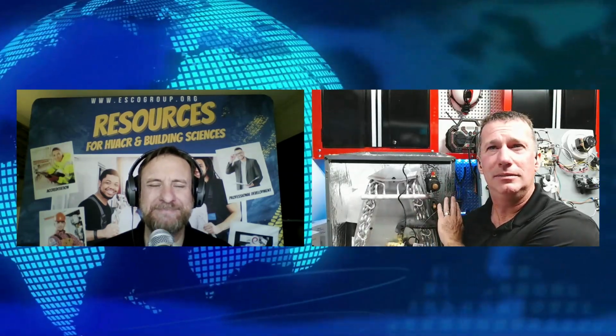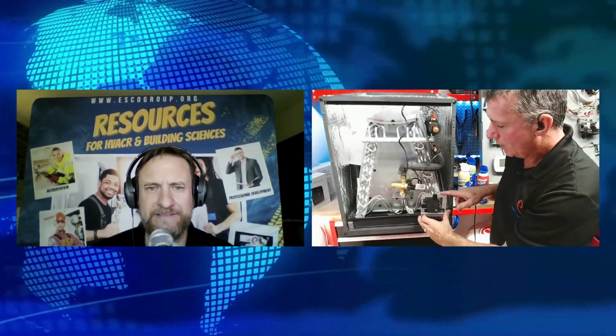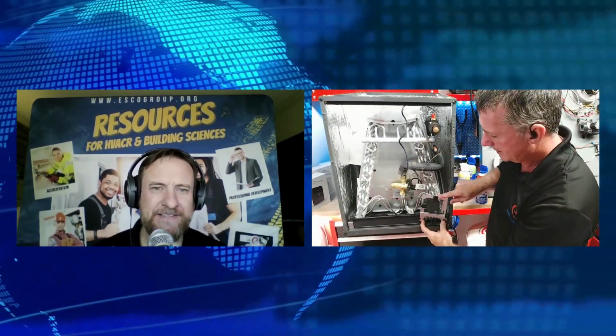So what we're actually going to work with here is a fresh off the shelf Goodman Amana Daikin 2-ton coil that is an R32 coil. So all of my local Johnstones are now stocking their 2-ton, 3-ton R32 split systems, the outdoor units and the A coils. And what we're going to see is this little mitigation control. It's an RDS, a refrigerant detection sensor. This RDS sensor actually sits on this coil, and it is rested over the drain assembly. And then on the front cover, it has a knockout in the door, and I'll show you that here in a little bit. But I wanted to bring this down so you can see the location of this.